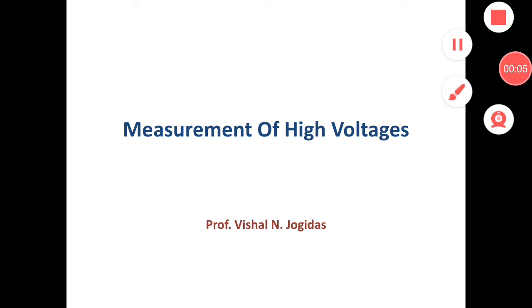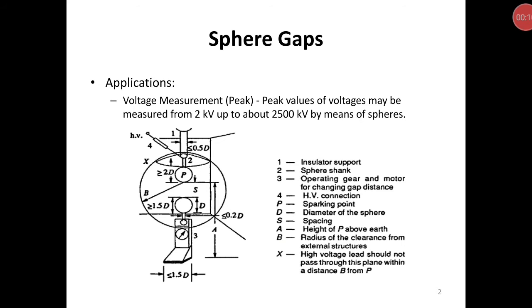Today we will discuss the measurement of high voltages. Sphere gaps. Generally, high voltages are measured using sphere gaps. Peak values of voltages may be measured from 2 kV to about 2500 kV by means of spheres. The figure shows the vertical arrangement of sphere gaps.